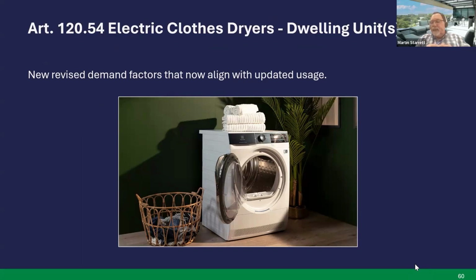Electric clothes dryers, dwelling units. The revised demand factors now align with updated usage. They're simpler now. Basically, it used to be 1 to 4 dryers at 100%, but now it's 1 to 2 dryers at 100%. So the table is a little bit simpler now. You still have to figure 5,000 per electric clothes dryer, but the demand factor table has changed. Next slide.